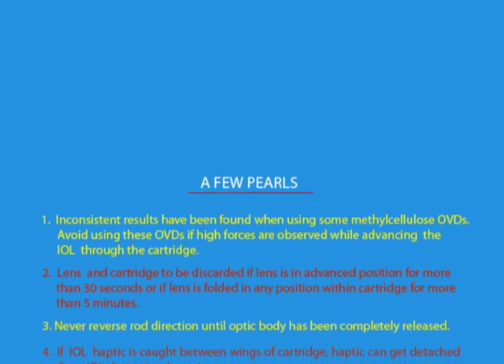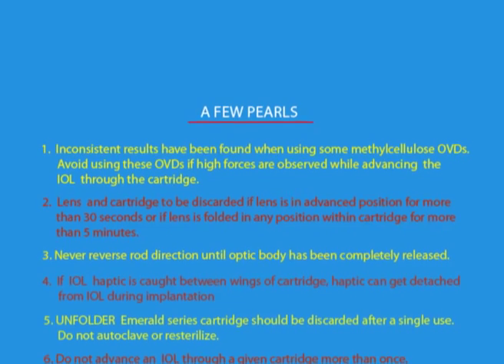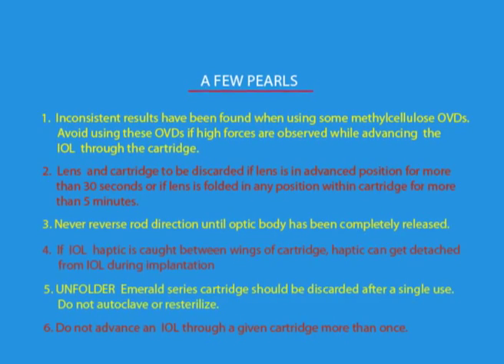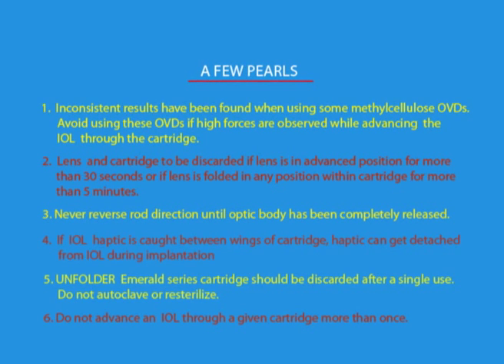A few pearls. Inconsistent results have been found when using some methyl cellulose OVDs. Avoid using these OVDs if high forces are observed while advancing the IOL through the cartridge. Lens and cartridge should be discarded if the lens is in an advanced position for more than 30 seconds, or if the lens is folded in any position within the cartridge for more than 5 minutes. Never reverse rod direction until the optic body has been completely released. If the IOL haptic is caught between the wings of the cartridge, haptic can get detached from the IOL during implantation. The Unfolder Emerald series cartridge should be discarded after a single use. Do not autoclave or re-sterilize. Do not advance an IOL through a given cartridge more than once.